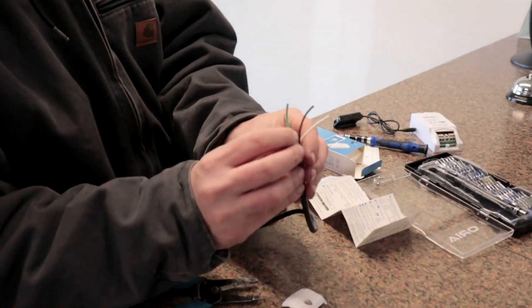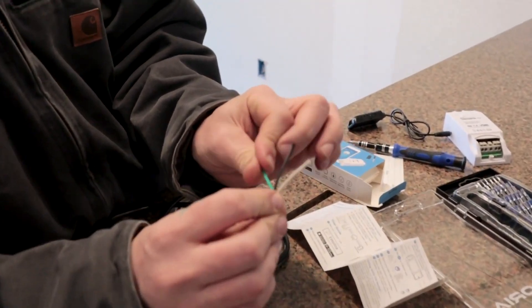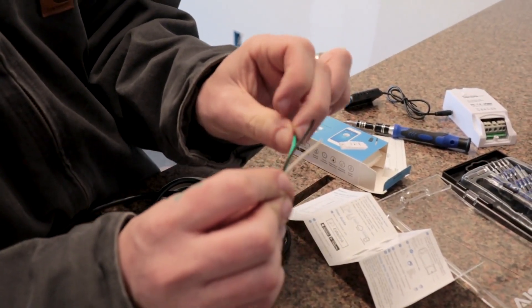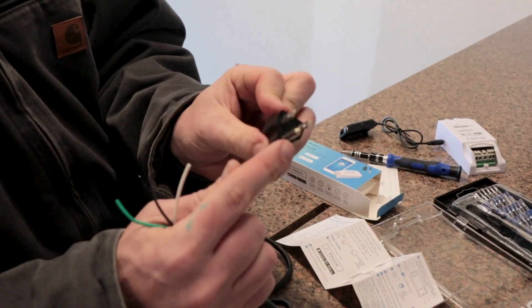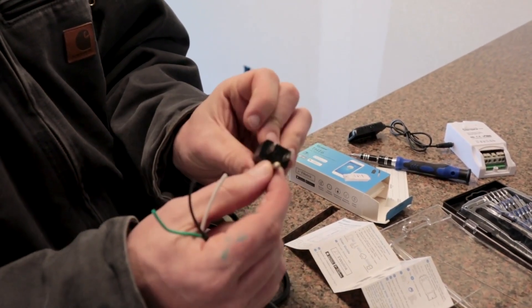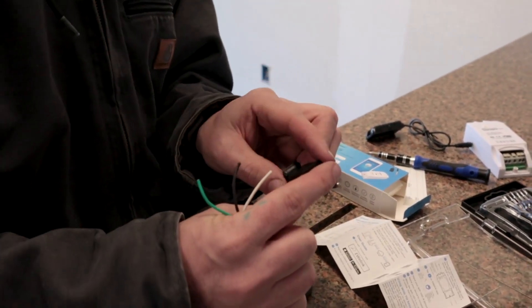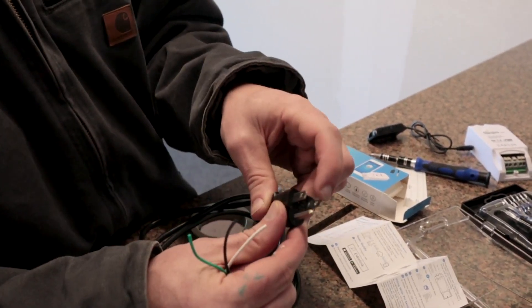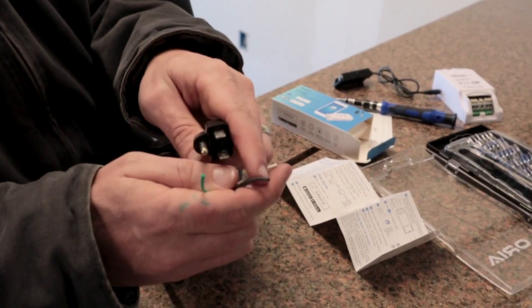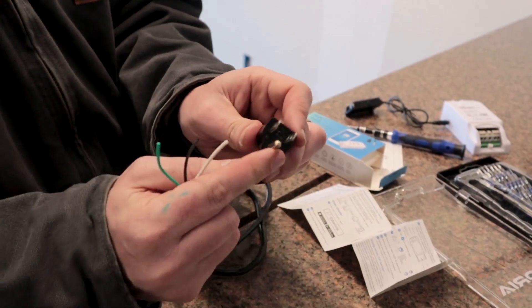So after this is stripped, we have three different wires. We have a black, a white, and a green. The green is ground or earth. So there's no power conducted on that. It's just a safety feature. It's going to be wired to this pin here, or this bar, I guess. And then we have, on here we have, what is it? The right, the left side is going to be our neutral. And the right side is our hot. So this one is the black. This one is the white. And this one here is the earth.